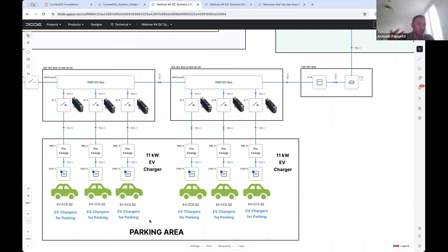To dive into this design a bit: there are three major elements. There's an AC/DC bidirectional converter, which we call the active front end or interlink converter. It's available in 50 kilowatt, 100 kilowatt, or multiples of 100 kilowatt, and I can parallel as many as needed at any location. I can have three containers at three different locations in the same parking lot, connected to the same bus using three different AFEs, or three points of connection.